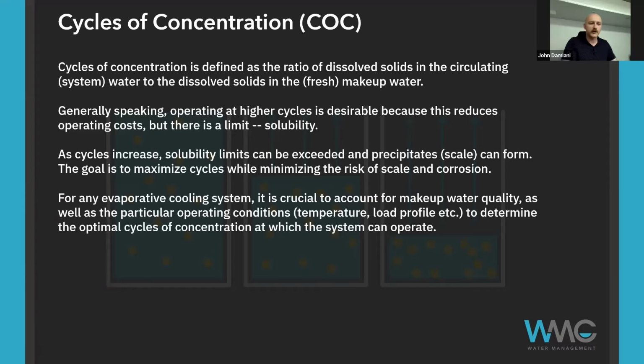So in a cooling tower application, we're talking about your freshwater makeup as it exists, and then what it looks like inside the cooling tower as it's circulating, okay? As we increase cycles, generally we want to operate at as high cycles as possible, and I'll show what that means. Running at higher cycles will reduce operating costs because you're using less water. There's less chemical to treat that water, less energy to reheat or recool that water, et cetera. So it's really crucial to account for the makeup quality and the operating conditions of the system. All these affect the maximum safe cycles that you can operate at.